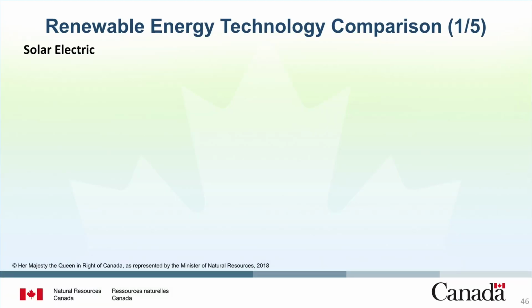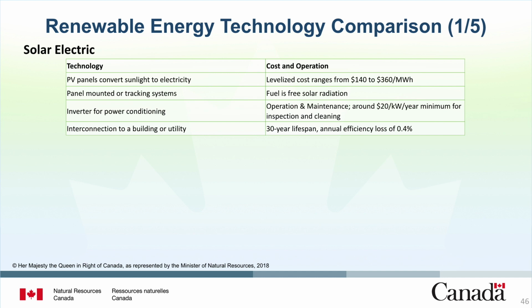Let's start with solar energy. Solar PV panels convert sunlight to electricity and can be found in panel-mounted or tracking systems. An inverter is used to conduct power conditioning and can be interconnected to a building or utility system. The levelized cost of electricity for solar electric technology, the average price a generator must cover over its lifetime to break even financially, ranges from $140 per megawatt hour to $360 per megawatt hour. The fuel for this system is free solar radiation. Operation and maintenance costs can be around $20 per kilowatt per year as minimum for inspection and cleaning requirements. The lifespan of these systems is around 30 years, with an annual efficiency loss of 0.4%.